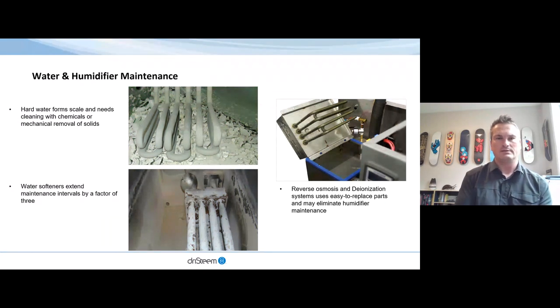Now, when we use soft water, soft doesn't mean that we've taken minerals out of the water. It just means that we've displaced the hard minerals, which are your carbonates, your manganese, your fluorides, things like that, now with sodium or potassium. And this may extend the maintenance intervals by a factor of 3, but there is still maintenance involved with that. To completely reduce the maintenance for up to very long intervals would be to apply reverse osmosis water or even deionized water. And these systems then alleviate the maintenance from the humidifier, typically to the water treatment side of things.